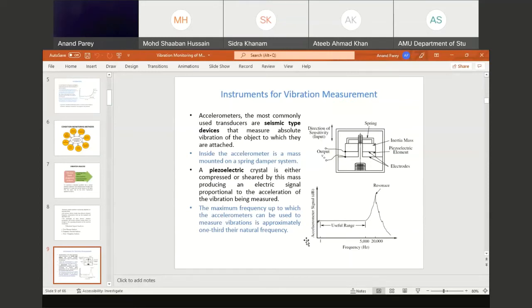For that, you need to know at what RPM the machine is running, and if there is any gear or bearing, what components of the fan or machine are there. Depending on the various mechanical components and the input speed, you can find out various frequencies associated with that input frequency, and their harmonics too - three or four harmonics you can take.